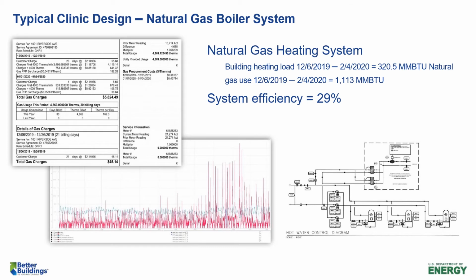So this is a little study that we did on another building this winter, and this heating system is effectively functioning at 29% efficiency. It might be a little better than that, maybe up to 40 or 50%, but you can see that's a tremendous difference from what the energy model says. Whatever the energy model said the natural gas consumption is going to be in this building, in reality it's actually going to be 2 or 3 times that.